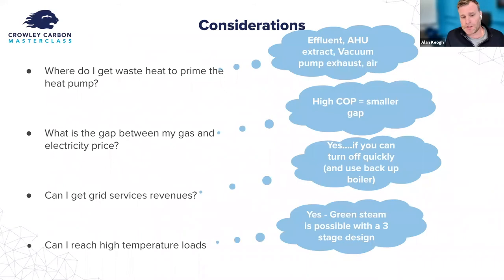So some of the considerations when you're looking to install a heat pump - there's more than this, but these are the main ones. A really critical first one is, where do I get waste heat from to prime the heat pump, which is to take some waste heat source, or ambient even, and then pump that to a higher, more useful temperature level, a better quality of heat. Some of the sources for waste heat are potentially effluent from your site - that generally tends to be 20, 30 degrees, depending on washdown and CIP etc. AHU extracts, vacuum pump exhausts, and also ambient air. In the summertime, hopefully the ambient's up to 15 or 20 degrees, that can be used to prime a heat pump as well.